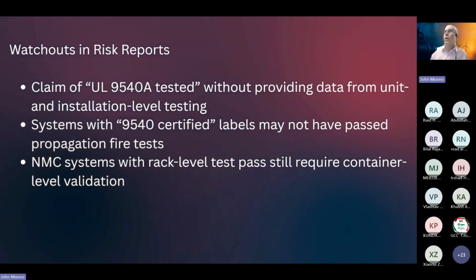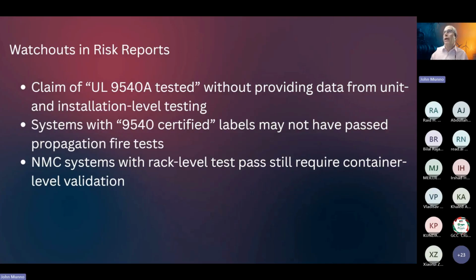So what you watch out for in risk reports are blanket claims that it's UL 9540A tested. What does that mean? Be careful about what that means. They've got to provide the data from the unit and installation level testing. And if it says 9540 certified, that doesn't mean it has passed propagation fire tests all the way to the installation container level. And nickel manganese cobalt systems with rack levels still require container level validation. So just because it passed at the cell or module level doesn't mean that it's really a safe system.